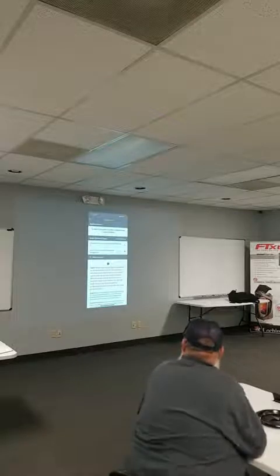Now we're at the measurements. The only thing we have to do now is take electrical readings off the piece of equipment. It's showing us there are some diagnostics here, so let's go back in and take a peek. It's telling us the system's operating with undetermined characteristics of liquid line temperature below the outdoor ambient. We have a liquid line that's 74 degrees and an outdoor ambient of 76 degrees. So it could be you're pulling short-cycling air or something around that probe.